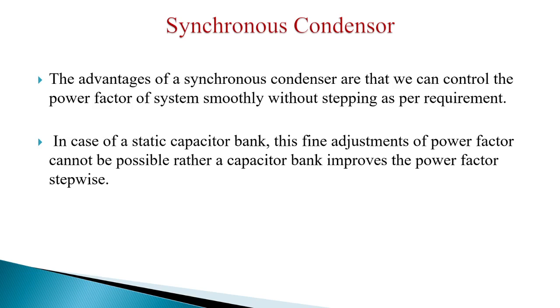So the advantage of a synchronous condenser is that we can control the power factor of the system smoothly, without stepping, as per requirement. In the case of a static capacitor bank, fine adjustment of power factor is not possible. Rather, a capacitor bank improves the power factor stepwise. So, fine adjustment can be done with a synchronous condenser, whereas power factor improves stepwise with a capacitor bank.